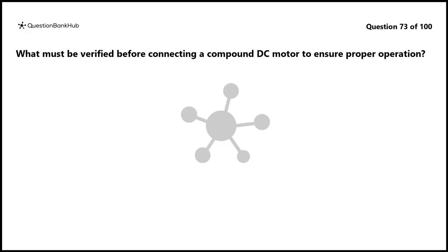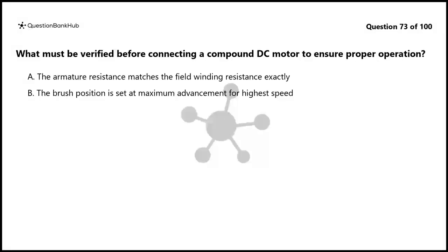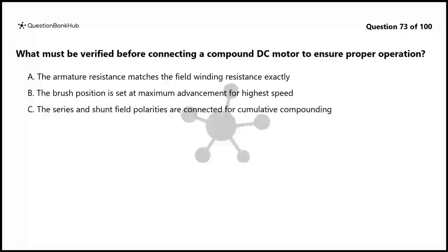Question 73. What must be verified before connecting a compound DC motor to ensure proper operation? A. The armature resistance matches the field winding resistance exactly. B. The brush position is set at maximum advancement for highest speed. C. The series and shunt field polarities are connected for cumulative compounding. D. The interpole windings are disconnected to prevent regenerative braking.